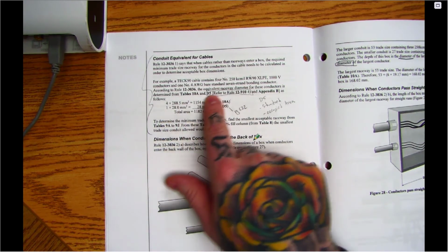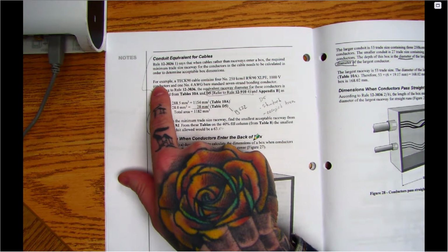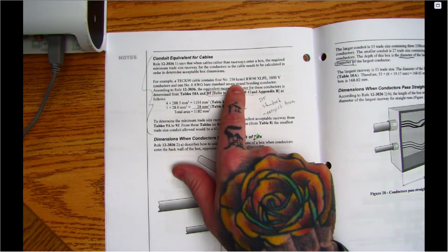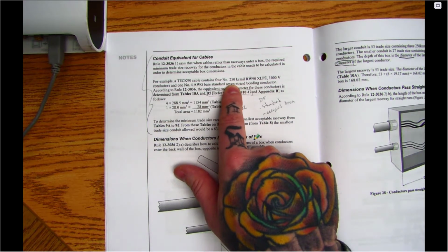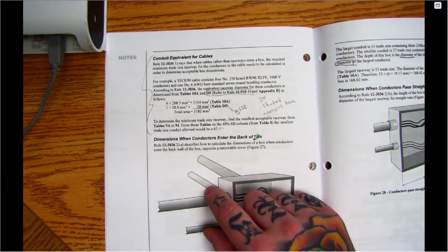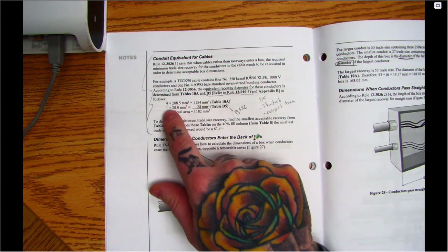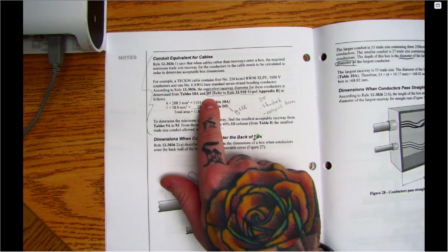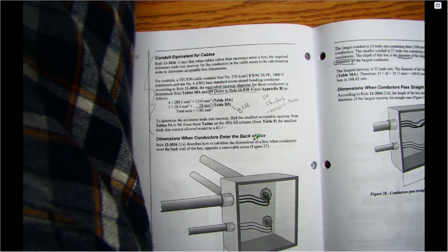It tells us to look at the wire size for the TECK. So if it's number 250 kcmil, we still go to table 10A to find out what the area is of those cables. And then a little thing we haven't talked about here yet is table D5. That's going to tell us how to do that bare stranded conductor. It's in the appendix, so that's where it tells you to go to D5. Just go to that rule and go to the appendix and it'll show it to you.